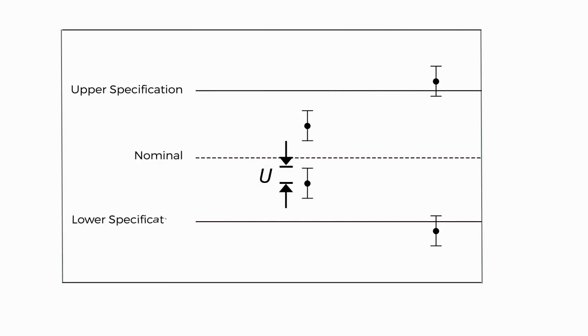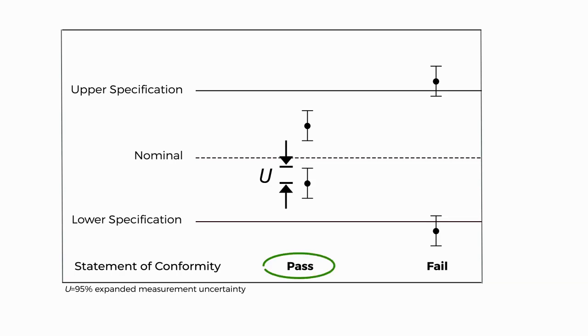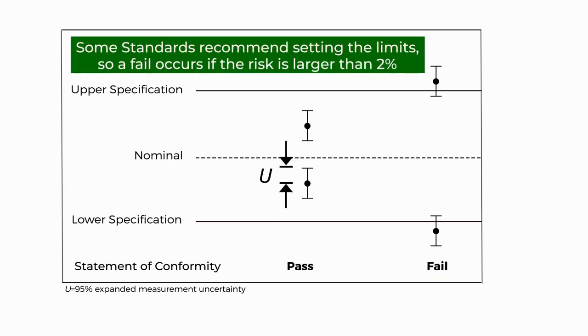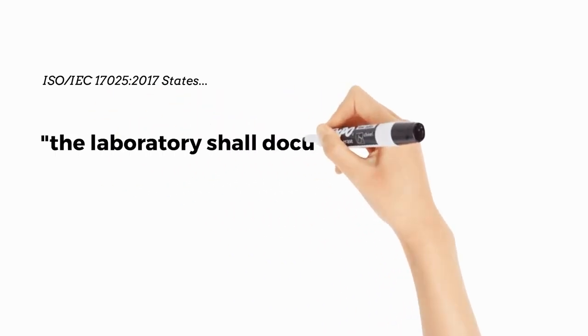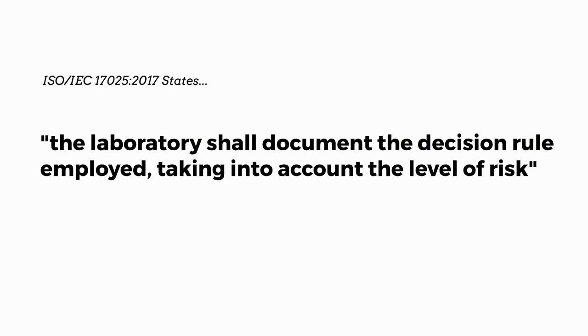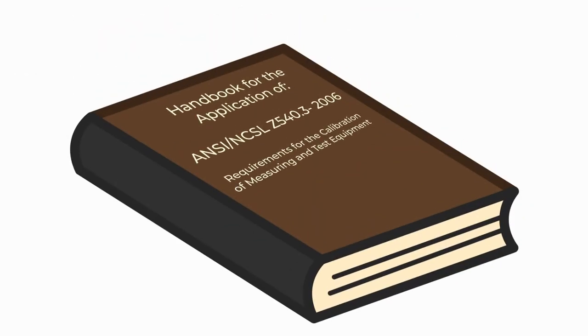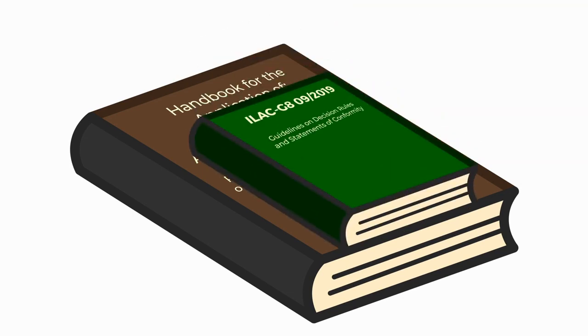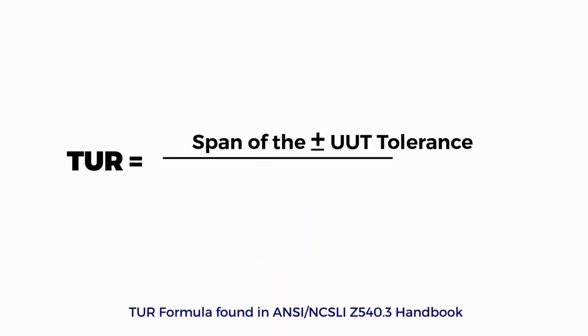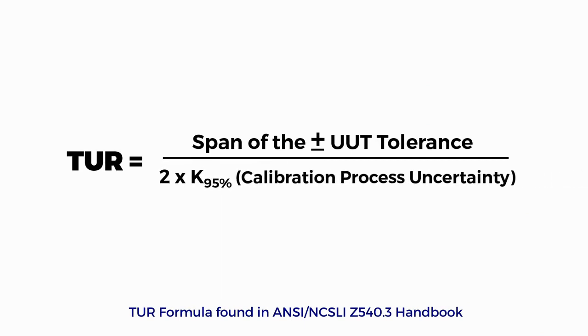Decision rules and TUR. When discussing decision rules, we describe how measurement uncertainty is accounted for when stating conformity with a specified requirement. The conformity for most is binary, meaning either a pass or a fail, and some standards recommend setting the limits so a fail occurs if the total risk is larger than 2%. The laboratory shall document the decision rule employed, taking into account the level of risk. Many of the decision rules found in documents such as the ANSI/Z540.3 handbook and the ILAC G8 use test uncertainty ratio, or TUR, to help calculate their measurement risk. TUR is defined in the handbook as the ratio of the span of the tolerance of a measurement quantity subject to calibration to twice the 95% expanded uncertainty of the measurement process used for calibration.